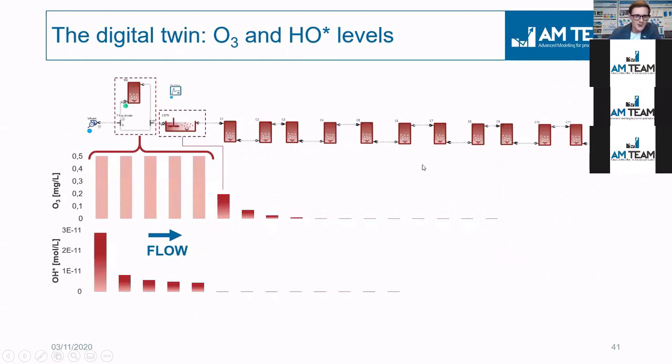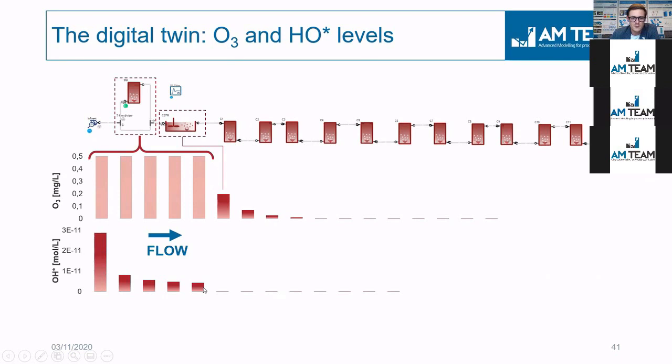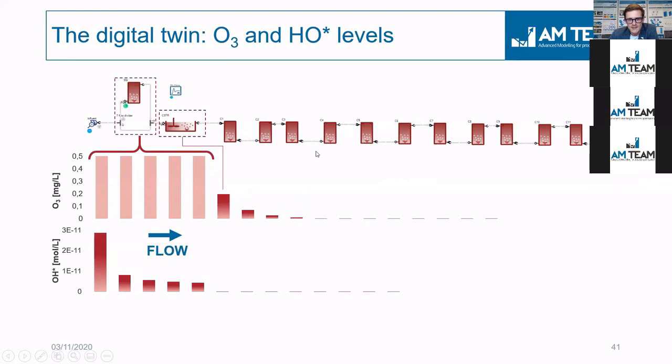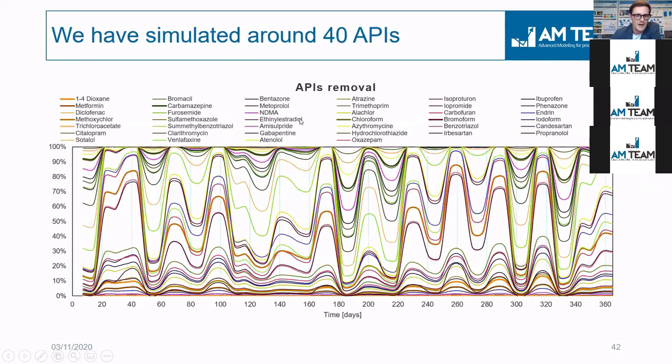So this is what Giacomo has been showing. I mean, you can look at ozone levels throughout the train, and you can see that specifically the hydroxyl radicals in a side stream, for example, but also right after injection, can be rather high. In this specific plant, the residual ozone was only very low, 0.2. And then you can see it disappears very rapidly if you go a bit further in the reactor.